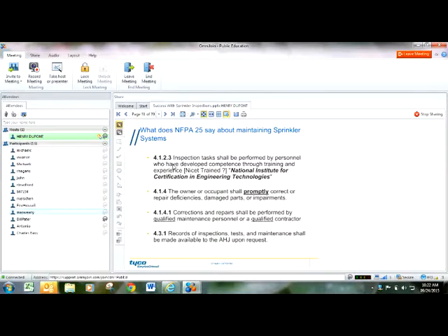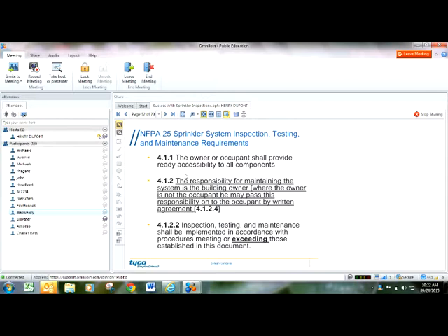What does NFPA 25 say about maintaining your system? It basically says if during an inspection deficiencies are found, the owner is required to take care of those deficiencies promptly. Furthermore, they have to be taken care of by qualified people. And the NFPA does not really go into a lot of detail about what is qualified. NFPA 25 says the responsibility for maintaining the sprinkler system is of the building owner. Where the building owner is not the occupant, that can be passed down to the occupant as long as it's done in writing. And this is kind of a good clause for sprinkler contractors. I'm glad that's in NFPA 25.